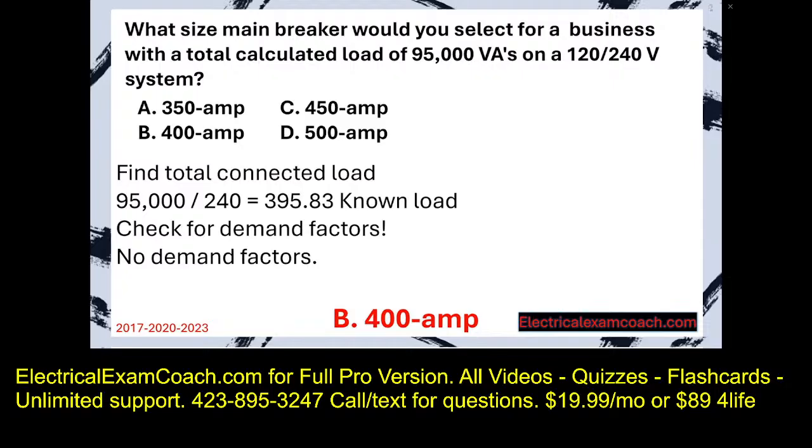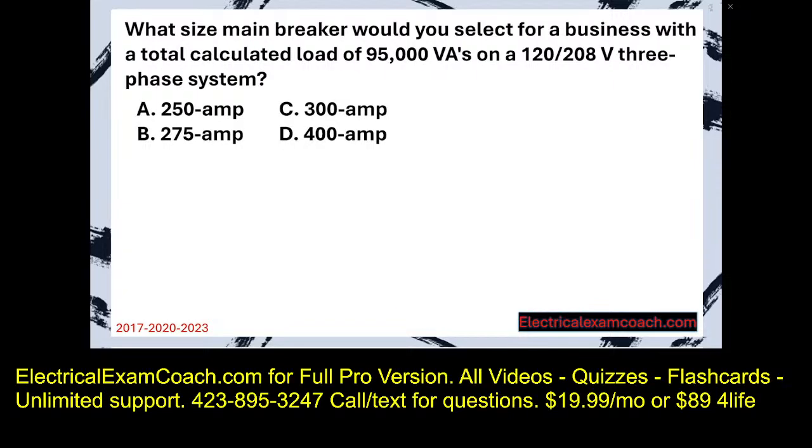Let's get to it. Now let's do that exact same calculation but on a three-phase system and show you the beauty of three-phase. What size main breaker would you select for a business with a total calculated load of 95,000 VAs on a 120/208 three-phase system?